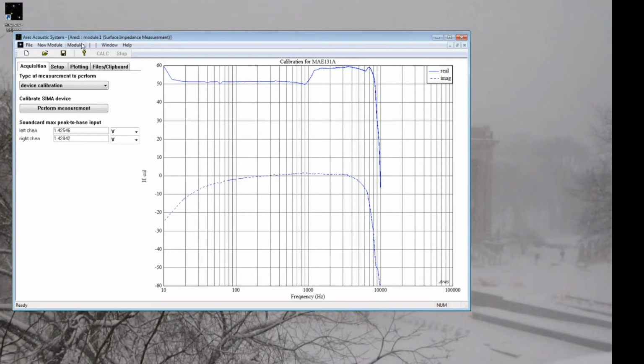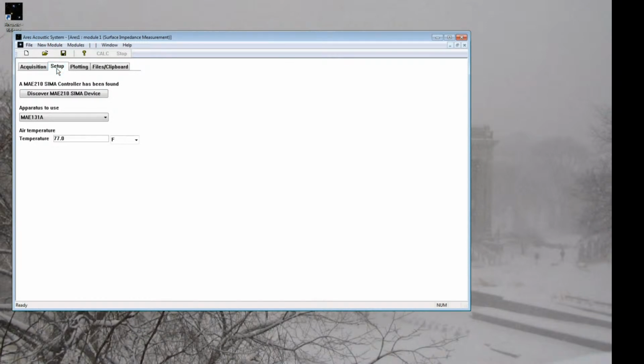First thing we need to do is make sure that we tell Ares we're using a 131, and that is the case here. In the Setup tab, we see 131 is selected. We also need to make sure it's found the SIMA controller. So right here it's saying a SIMA controller has been found. So we're good to go. That's because we've plugged it into the USB already. And we want to enter an appropriate temperature for the air in the room that you're doing the measurements in. 77 is usually fine.